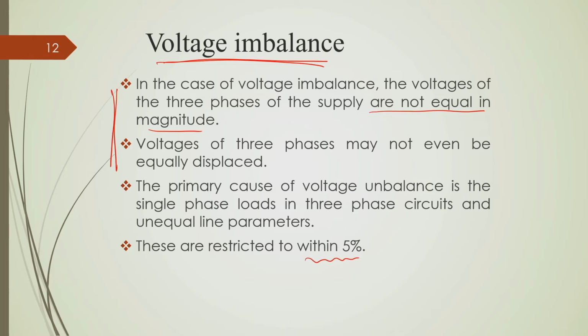Okay. So, what are the causes of this voltage imbalance or voltage unbalance? These are due to the presence of single phase loads in the 3 phase circuits, particularly on the secondary side of the distribution networks, where we have more domestic customers and they need a single phase supply. Okay. But electric utilities generally balance the loading of the individual phases.